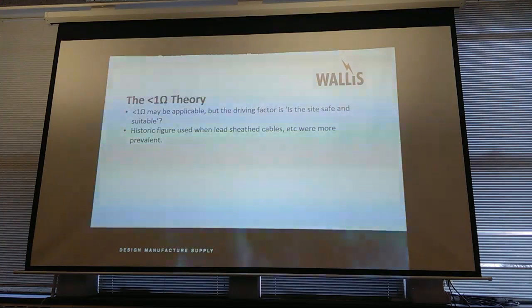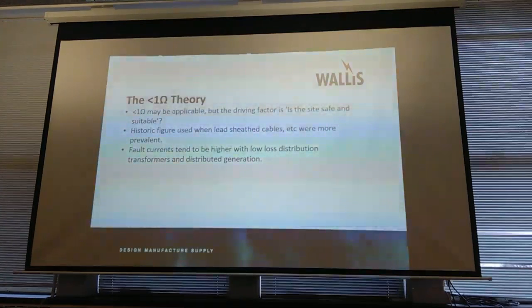Well, unfortunately, they've ripped all these lovely lead sheath cables out and put triplex in everywhere, or EPR cable, I think that Western Power use now. So you've lost all that global earthing system. Fault currents are tending to be higher. The DNOs are putting in low loss transformers. Where there's heat, there's losses, so they're putting the low loss transformers in. Problem with that is they are lower impedance, historically. If they're lower impedance, then you tend to get higher fault currents. If they're higher fault currents, it causes me, as an earthing engineer, quite a few problems.